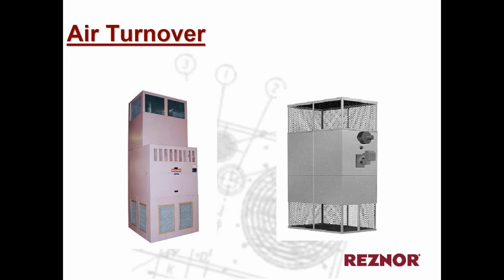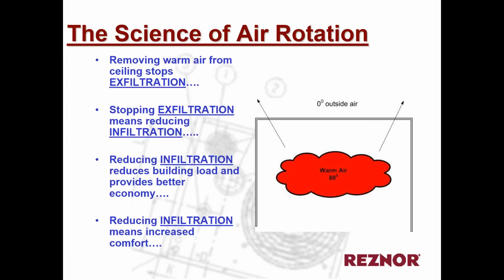Air turnover or air rotation units are very large heating and cooling units, particularly heating, that provide very comfortable heating in a large space. The science behind air rotation or air turnover is being able to turn over or rotate that air in the building at least 1.5 to 2 times for heating. That removes the warm air that typically stacks up in the ceiling and helps stop exfiltration. Exfiltration is when that warm air wants to go to the outside, which is colder. Hot air wants to go to cold. When we stop exfiltration, that stops infiltration, and when we reduce infiltration, that reduces the heating load on the building.